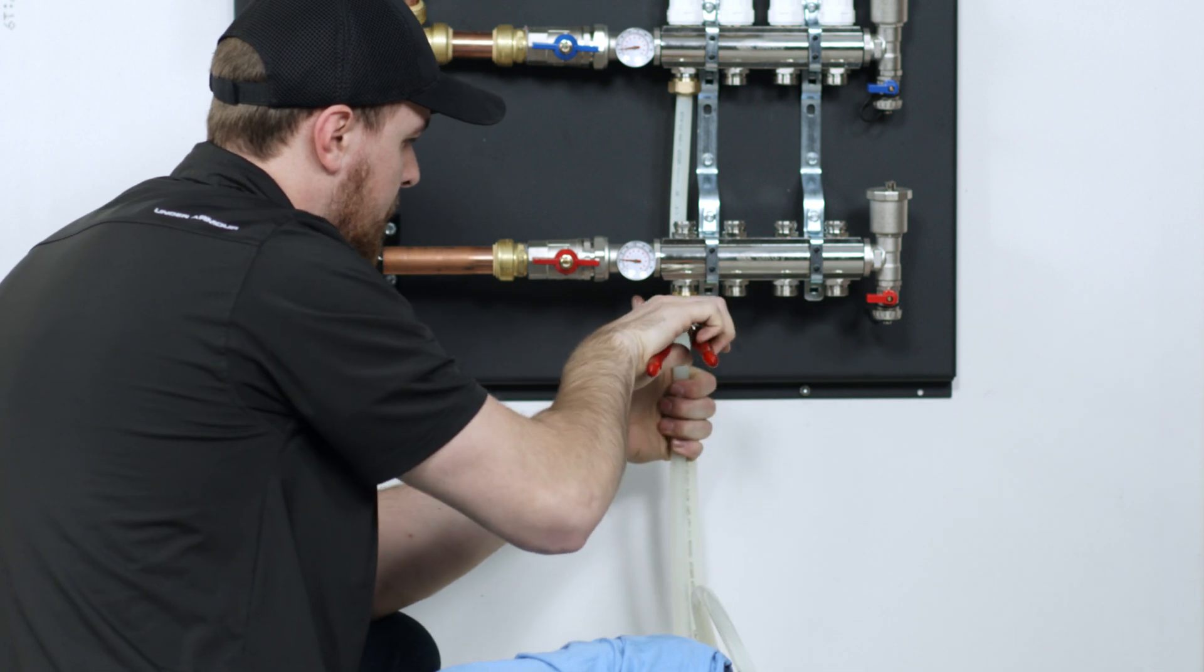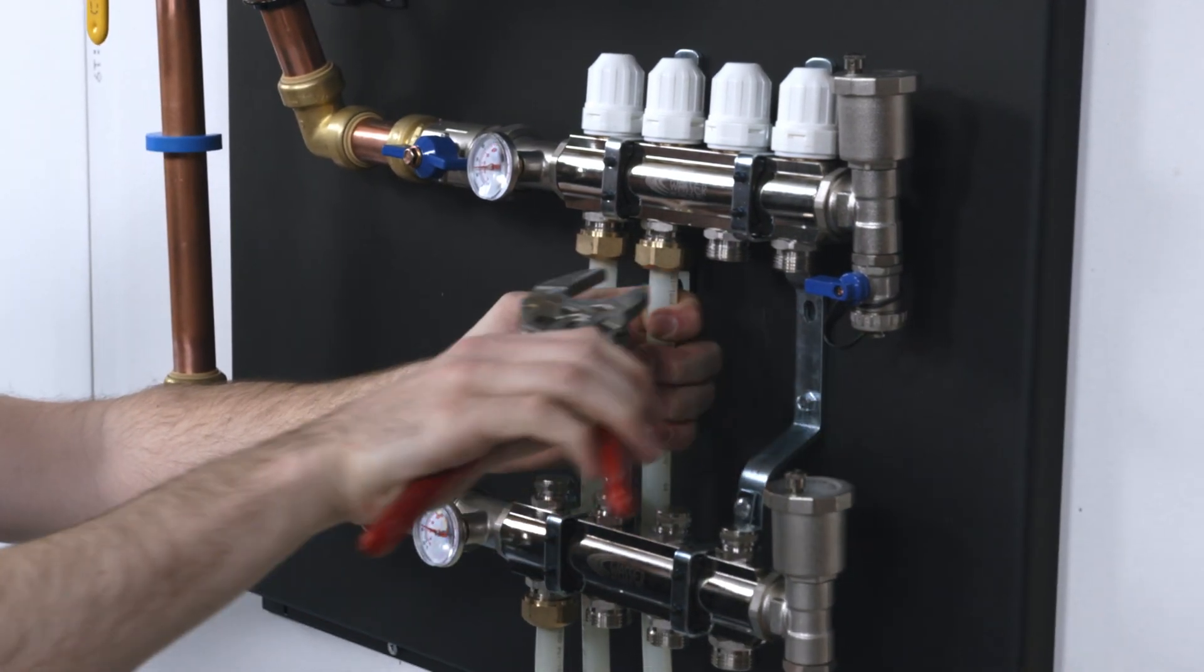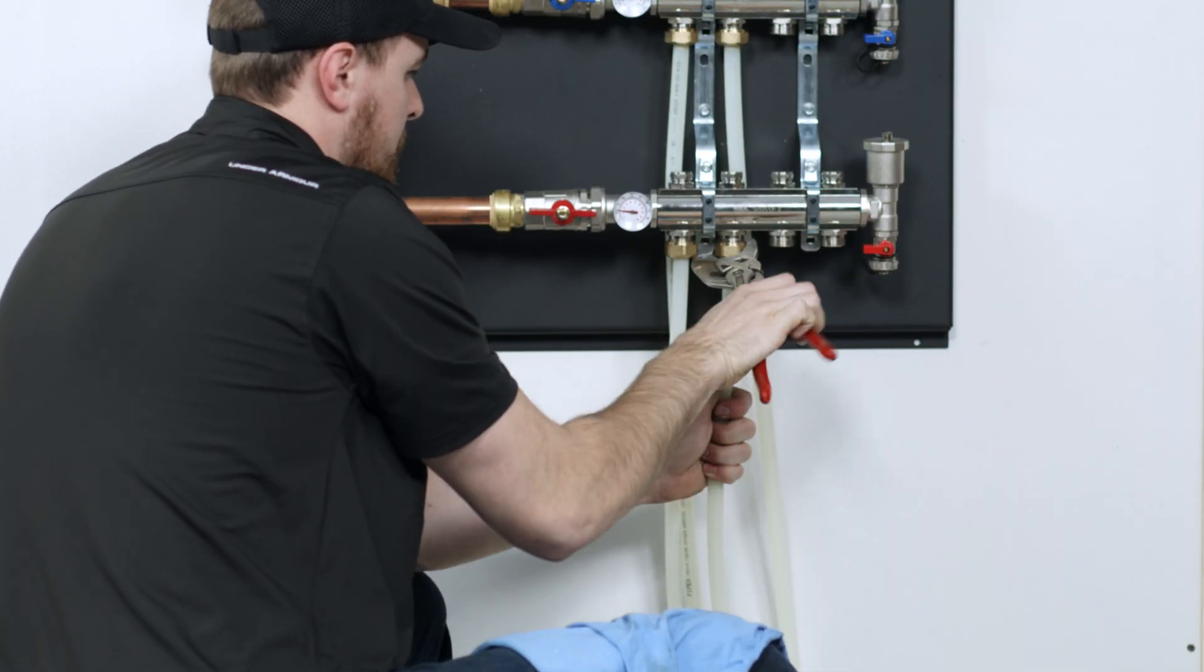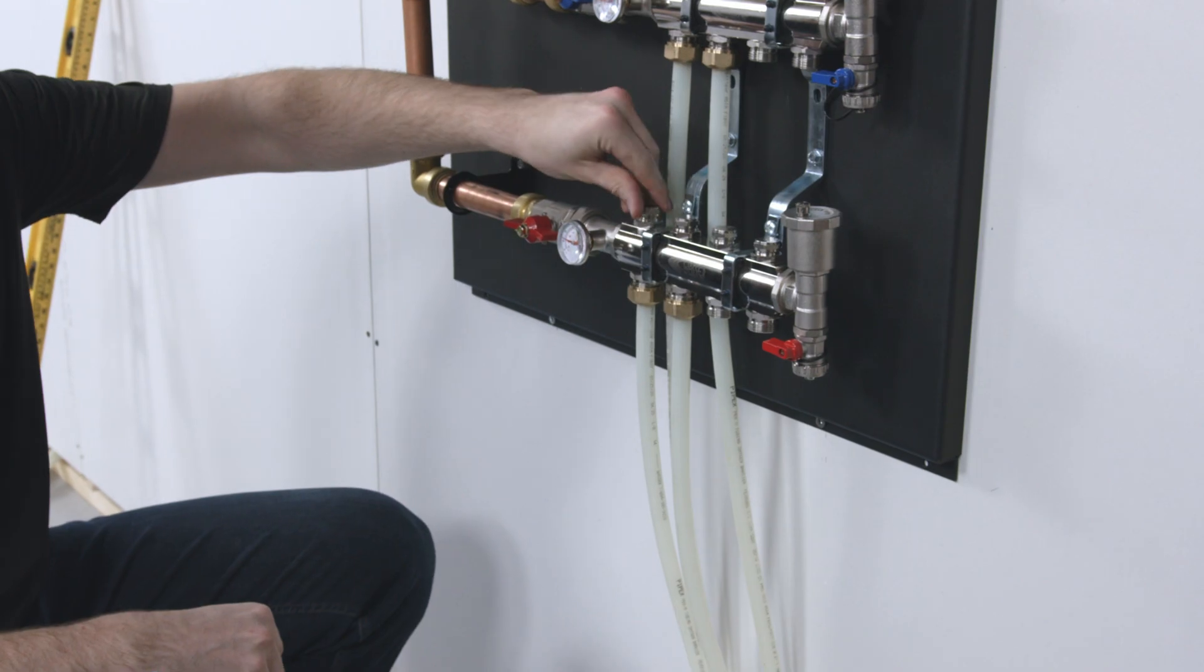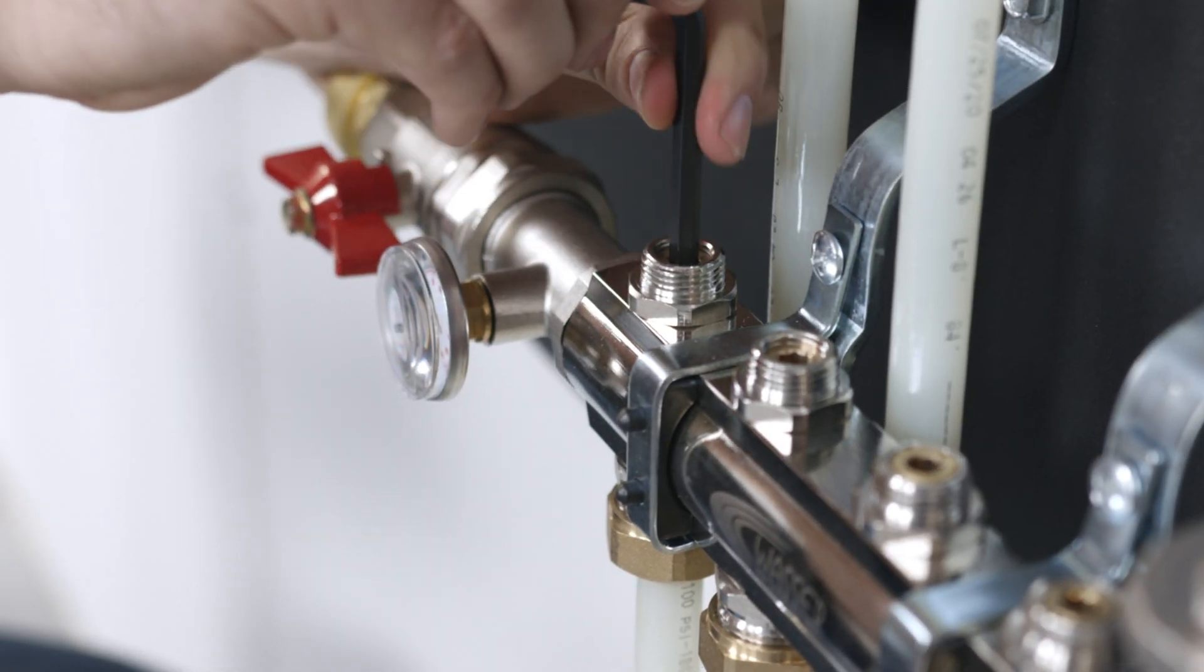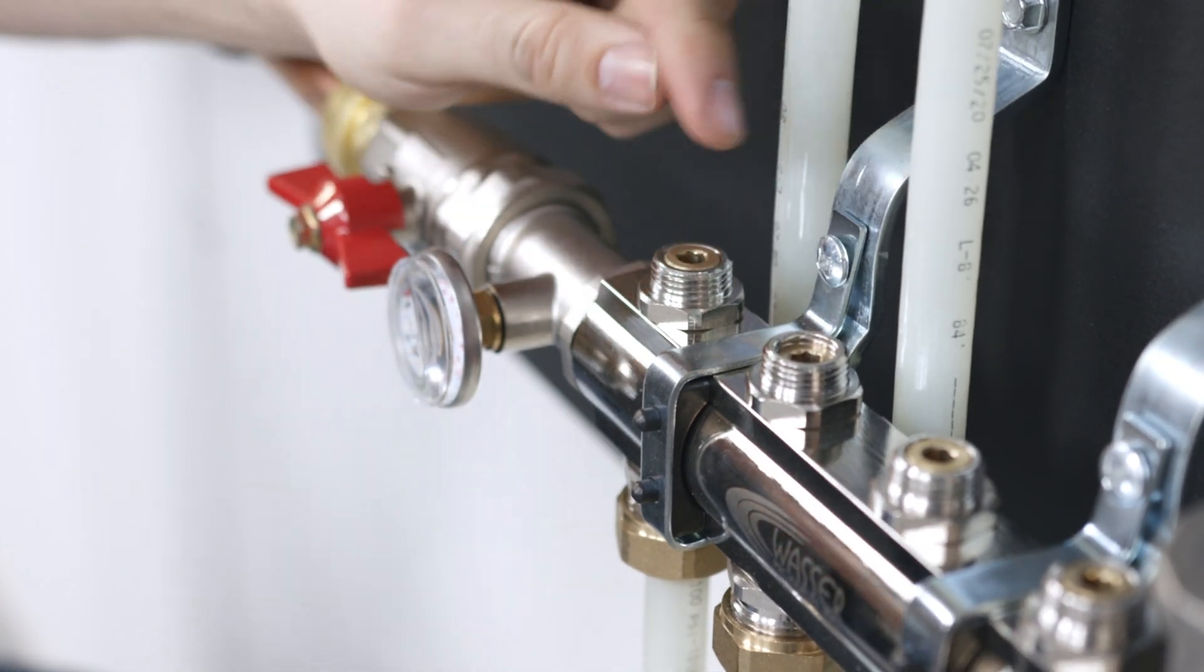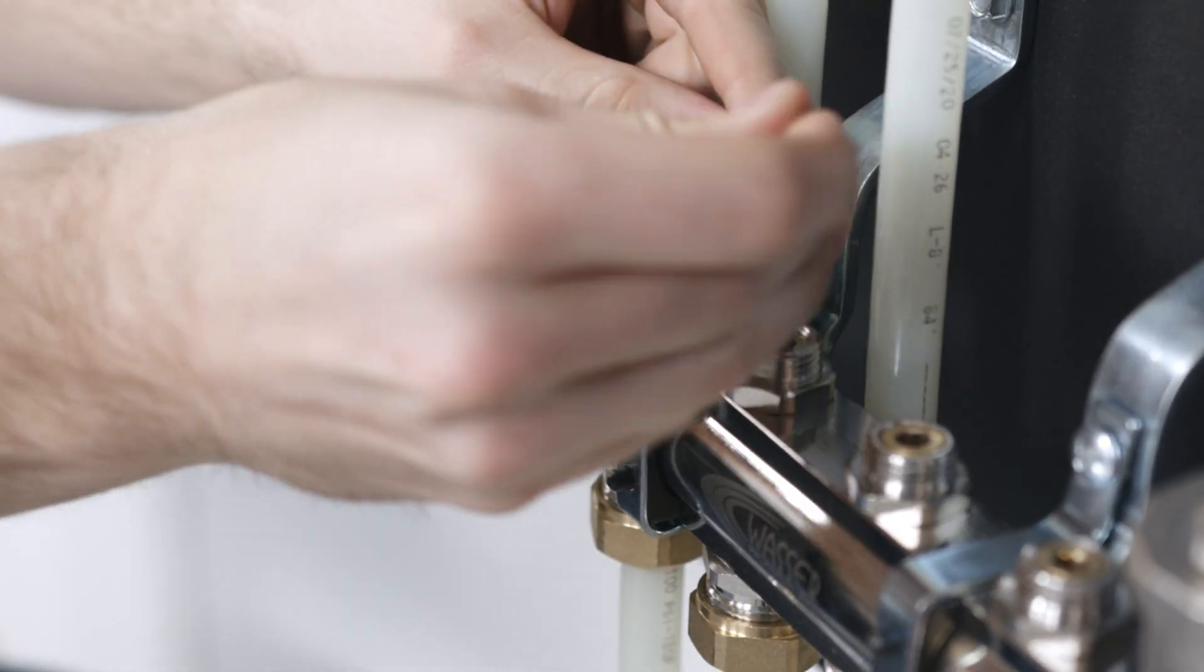Snug the manifold adapter nut with a wrench. Be careful not to over tighten. Open the manifold valves with an Allen key under the hex cap on the manifold. It will be fully open when it is flush with the top of the threaded seat.